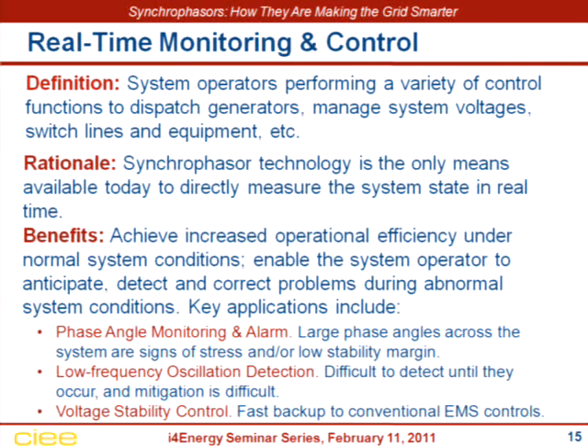Synchrophasors have some promise in being able to not only detect what's going on, but where the problem areas are, and in the future possibly serve as input to a control system where you might have storage or other controllable devices on the system, putting power pulses into or out of those systems to counteract the oscillations and have an active control system, informed with synchrophasor data. And then there's voltage stability.